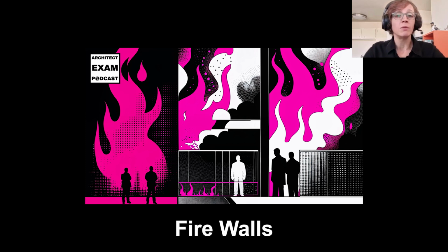And then in terms of materials, what do you use for a firewall? Typically, you use non-combustible materials. So you think about concrete or masonry for a firewall. For example, a thick concrete wall extending up beyond the roof. And that's your firewall. And that's how you can distinguish that it's a firewall. It's vertically continuous. So where can you find more information on this in the IBC? If you check section 706, you'll find all the information you need on firewalls.